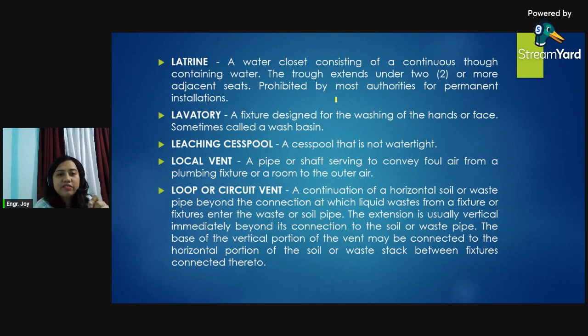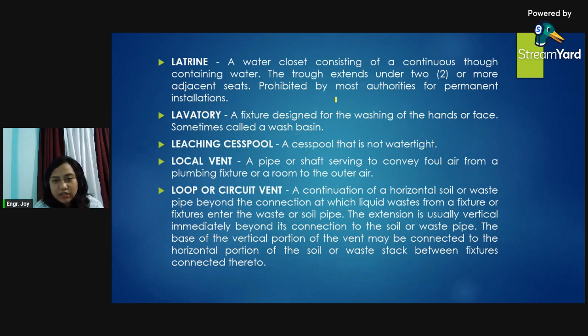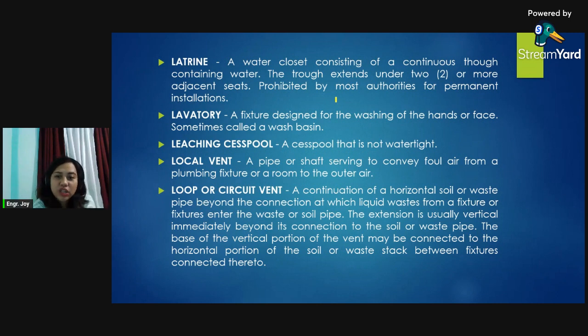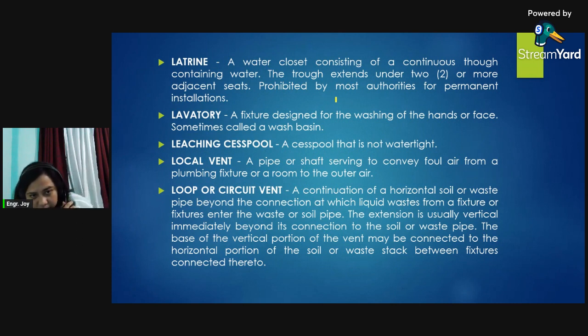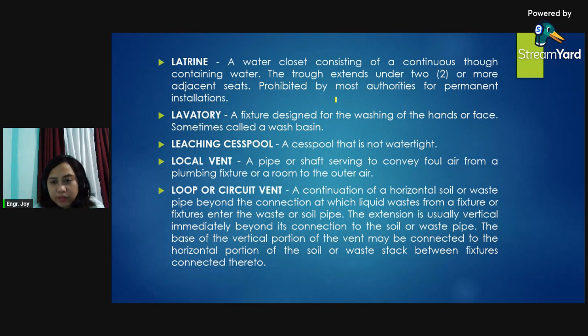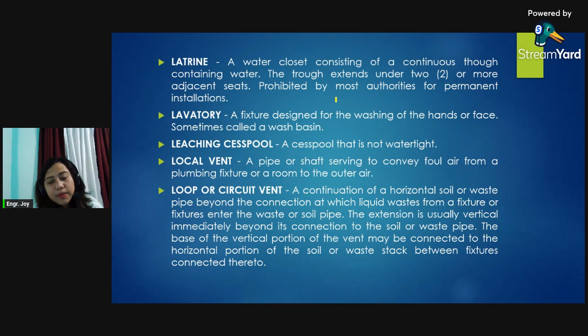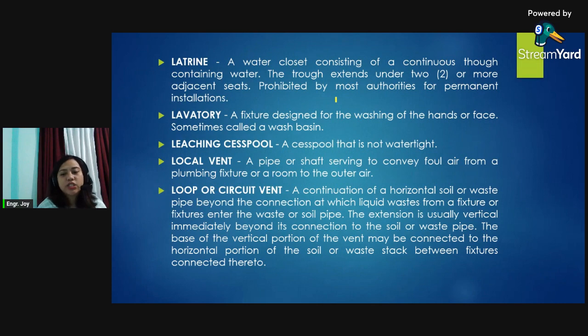Local vent: a pipe or shaft serving to convey foul air from a plumbing fixture or a room to the outer air. Loop or circuit vent: a continuation of a horizontal soil or waste pipe beyond the last connection to which liquid wastes from a fixture or fixtures enter the waste or soil pipe. The extension is usually vertical immediately beyond its connection to the soil or waste pipe. The base of the vertical portion of the vent may be connected to the horizontal portion of the soil or waste stack between fixtures connected thereto.